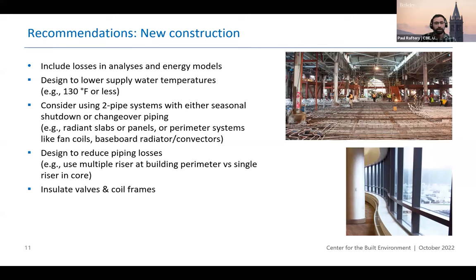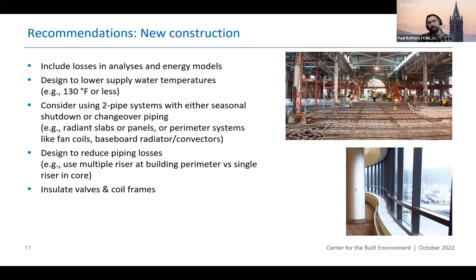In new construction, it makes sense to consider these losses as part of your analysis, and it gives you one more reason to design to low supply water temperatures. Designing to low supply water temperatures inherently means you'll get lower return water temperatures and your heating plant will operate much more efficiently. It also sets you up for the inevitable electrification of heating end uses in buildings. So whether you're designing for a heat pump system or a boiler today, you should be designing to 130 anyway — either you will have a condensing boiler, or in the future someone will want to use a heat pump to service that load, and it will be much easier if all the thermal equipment is sized for 130.